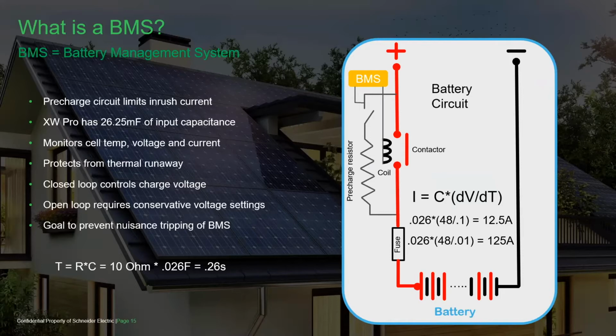So the inrush current calculation is capacitance times the delta of voltage, divided by the delta of time. So when you close a switch, the moment the two contacts touch each other, that determines your divisor for your dV over dt.